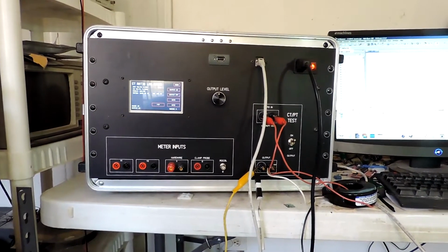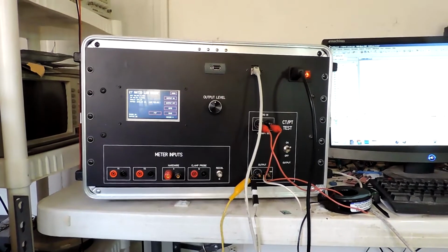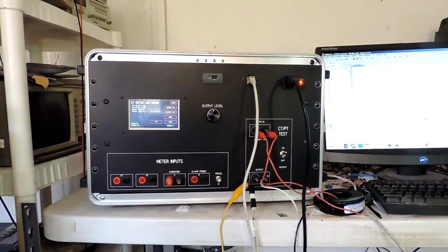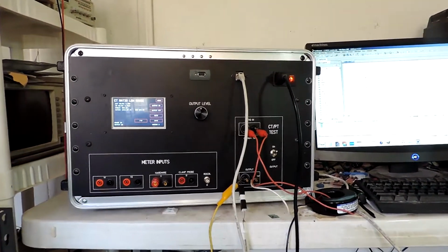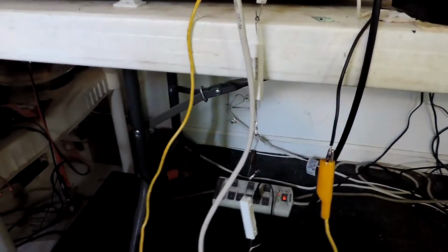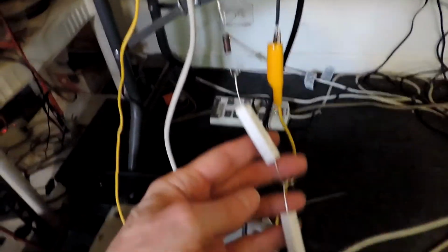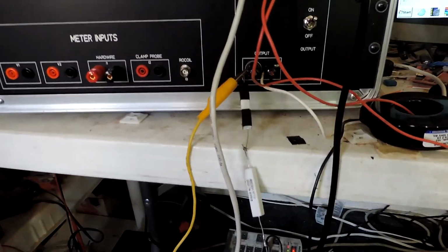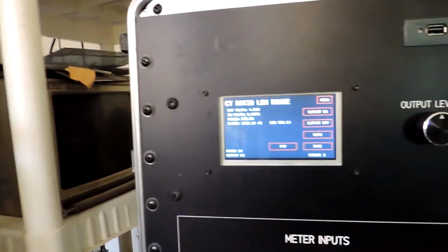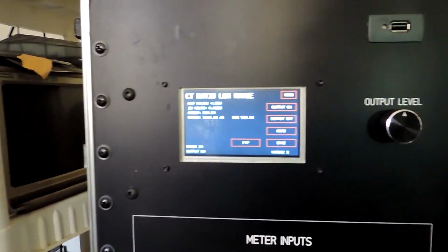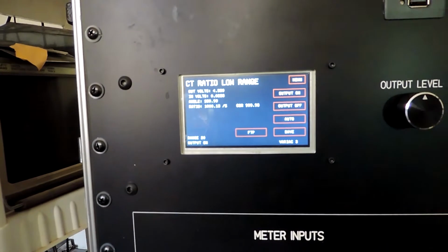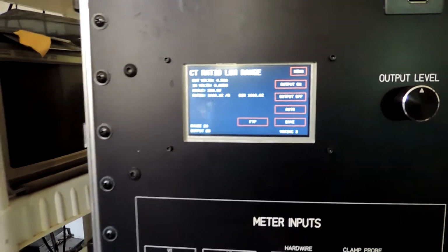Okay, this is a little video to demonstrate the efficacy of the CTMP 2020 winding and lead resistance compensation. Down here I have a string of 0.05 ohm resistors that I can insert different lead resistance. On the screen right now, of course this jumper counts too, I have the ratio with it clipped right to the binding post.